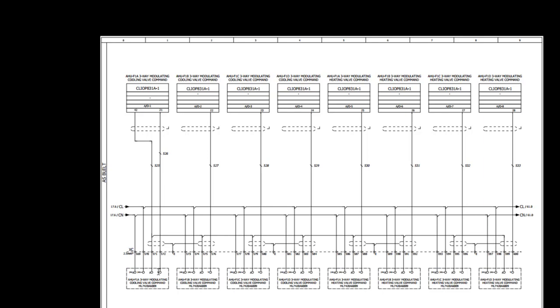So here you can also use 3 wires. Here 4 wires are shown, but since this 24 volt common of the module and the transformer power supply are the same, we can use 3 wires for the command also. Like common will be only 1 wire, and then 24 volt power and output signal. So no need for the 4 wires, but since it is done in this drawing, we are using that. But in your case, if your 24-volt power common and the common of the module are the same, you can use 3 wires only. So all other analog outputs are the same.